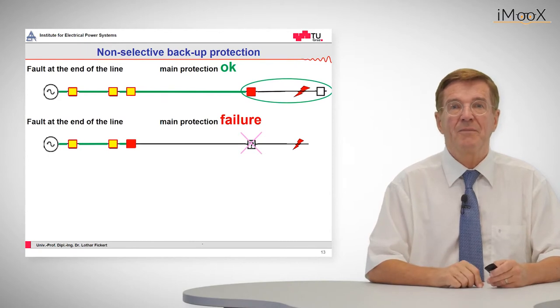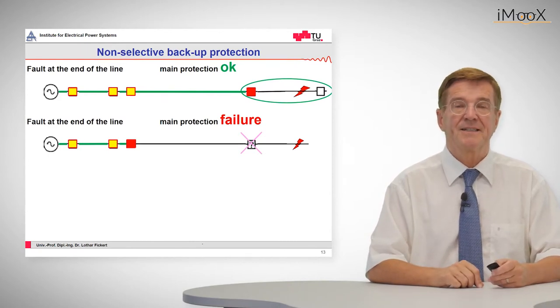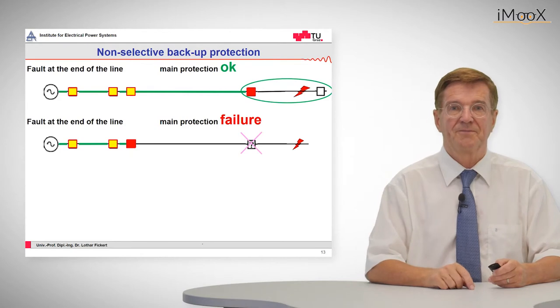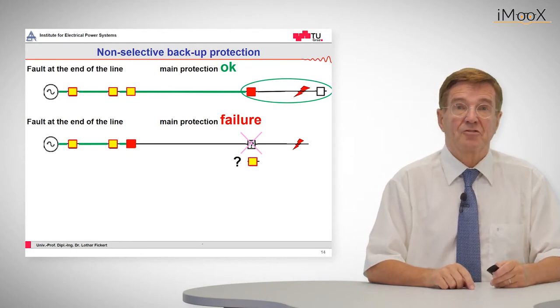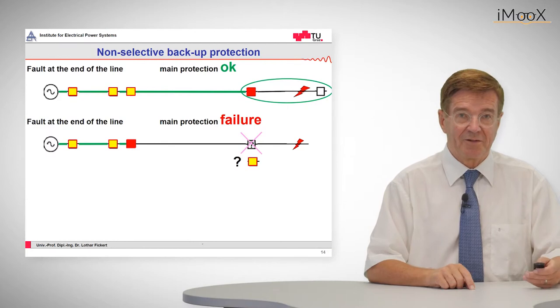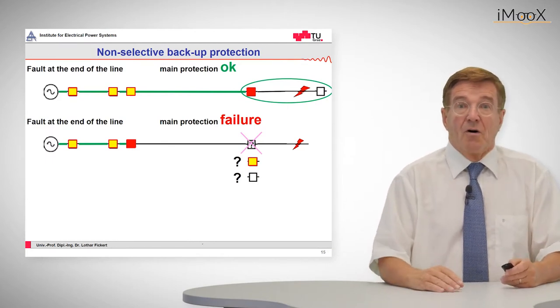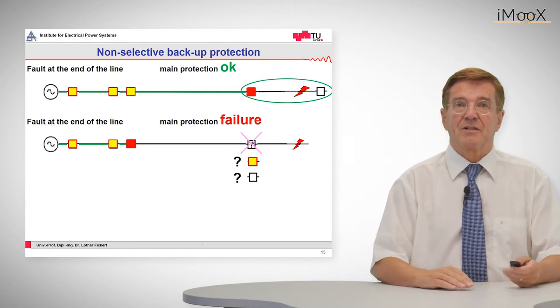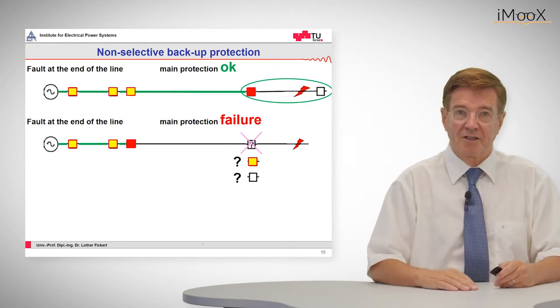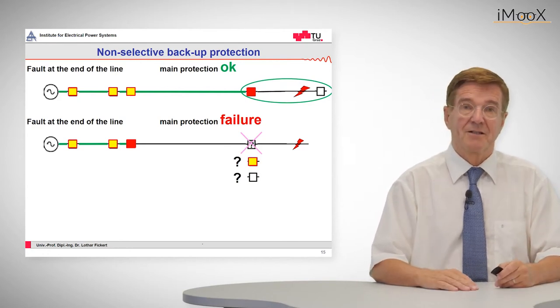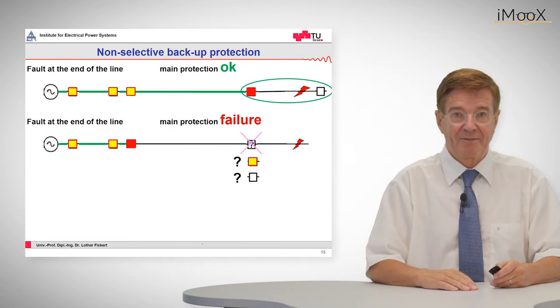But now we have a main protection failure, as indicated by these crossed arrows. Either we have a trip error, that means the relay will pick up but not effectuate a circuit breaker trip, or maybe it will not pick up at all. For example, due to shorted current terminals or failure of operation or whatever it may be.